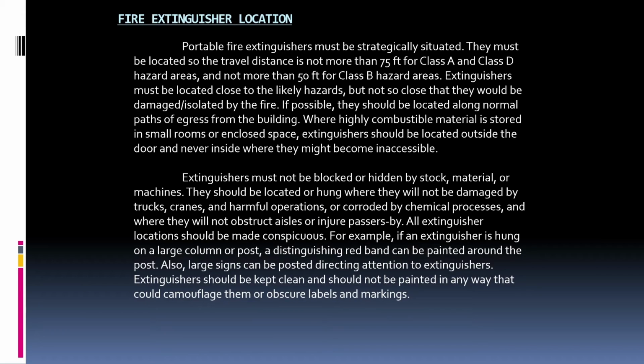Fire extinguisher location. Portable fire extinguishers must be strategically situated. They must be located so the travel distance is not more than 75 feet for Class A and Class D hazard areas, and not more than 50 feet for Class B hazard areas. Extinguishers must be located close to the likely hazards, but not so close that they would be damaged or isolated by the fire. If possible, they should be located along normal paths of egress from the building, where highly combustible material is stored in small rooms or enclosed space.